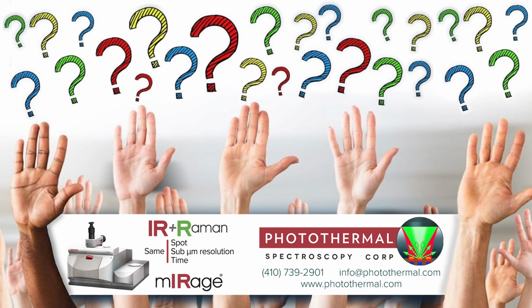So we still get excellent signal-to-noise in the infrared for OPTIR. At that point, any simultaneous Raman won't work because the Raman excitation powers are too low. But yes, samples that are typically damaged by Raman and where you have no other choice can be measured with OPTIR using this APD detector at tens of microwatts of power.